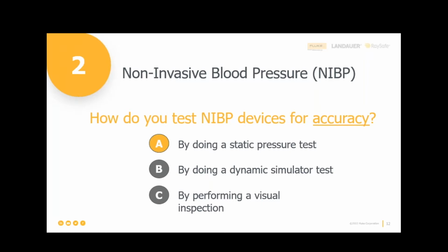So the answer is we have to do a series of static pressure level tests in order to determine accuracy. And that could include the cuff and hose wrapped around a mandrel or something solid so that we can pump it up to specific pressures. Now, it means the system has to hold pressure, right? So you're going to do a leak test first to make sure you can hold pressure. And then the safety part of testing for NIBP has to do with the automatic and effective release of the opening of the relief valve, so that the patient's arm and tissue doesn't get damaged because of a cuff that gets too tight and stays too tight.